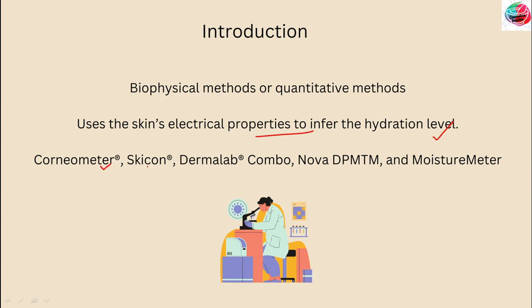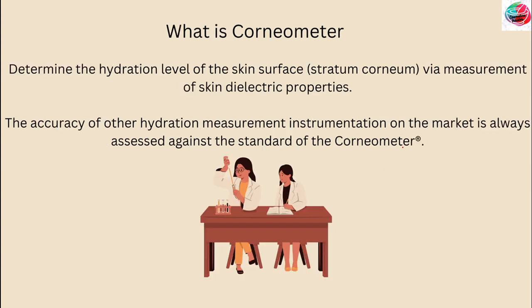Examples of such devices are the Corneometer, Skicon, DermaLab Combo, Nova DPM™, and Moisture Meter. The Corneometer is the world's most famous skin hydration measurement instrument. It is defined as an instrument that reproducibly and accurately determines the hydration level of the skin surface — that is the stratum corneum — via measurement of skin dielectric properties. The accuracy of other hydration measurement instruments on the market is always assessed against the standard of the Corneometer.